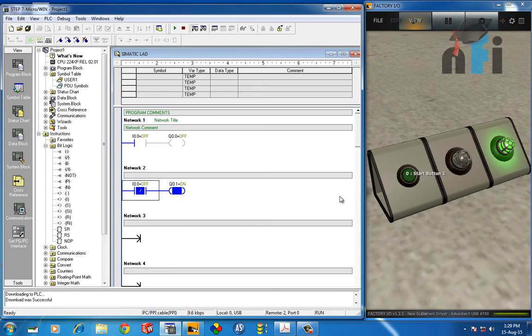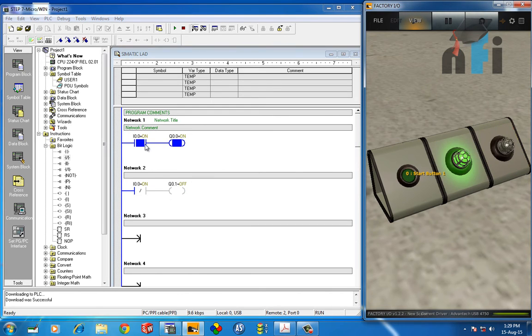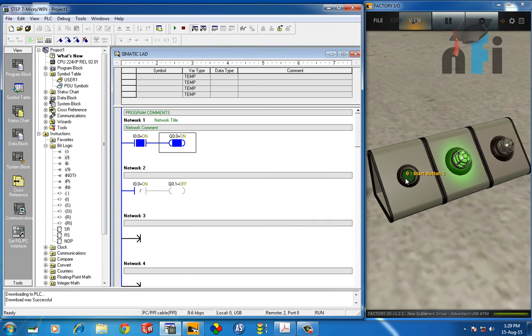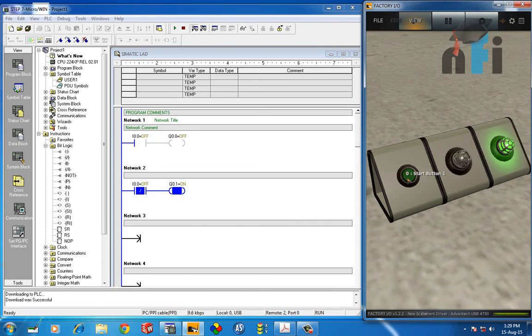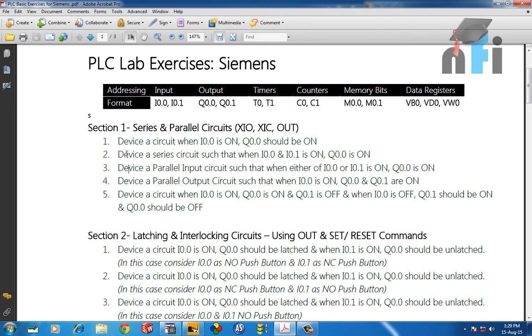Initially, you can see that when I0.0 is OFF, Q0.1 is ON. This is because the NC contact has not been actuated by I0.0, so it is true and the output is ON. When I turn ON the input, the NC contact becomes false so Q0.1 goes OFF, and the NO contact becomes true so Q0.0 goes ON. That's alternating the outputs using one input.